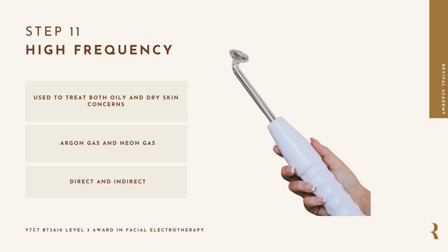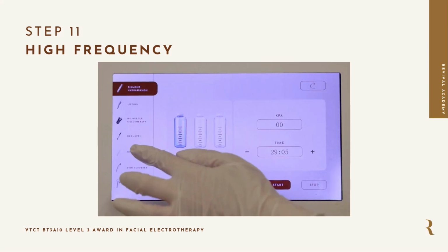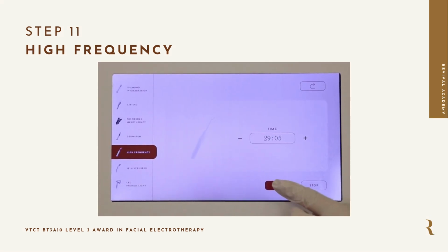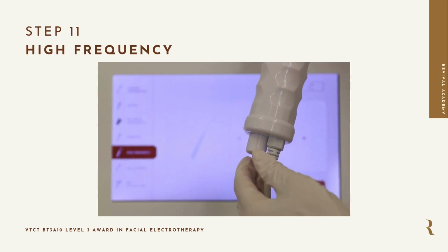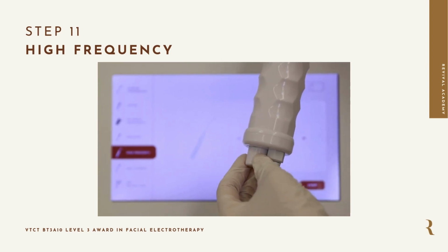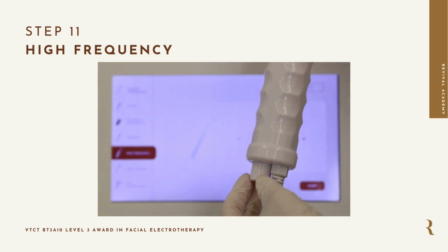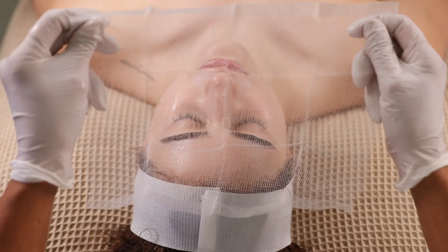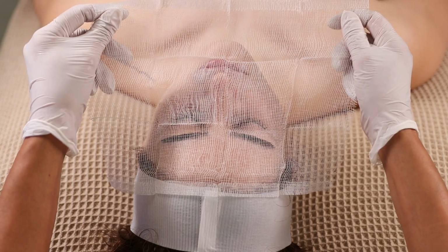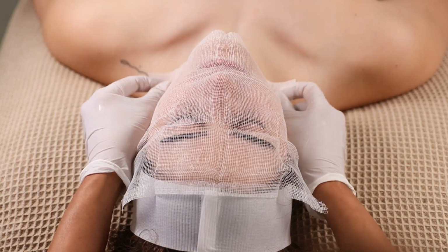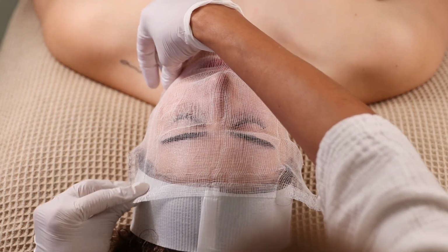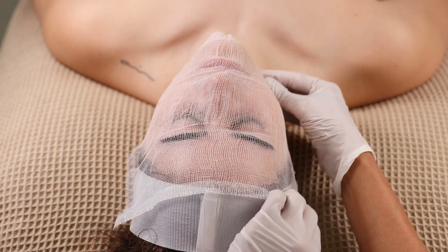Now we are going to move on to the next step, which is using the high frequency probe. Select the high frequency from the menu and press on the start button. You can adjust the intensity of the probe by rotating the button on the end of the probe. Before going ahead with the high frequency, unfold a gauze, place it onto the client's skin and then adjust the corners. Make sure that the gauze is actually fit to carry out the high frequency.